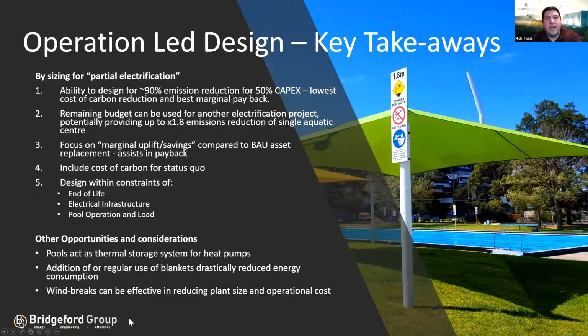So we've got a few key takeaways here, and we're terming this operation-led design. By sizing for partial electrification, you can put in a heat pump that doesn't fully electrify the site, sizing it for, say, half capacity, 800 kilowatts instead of 1600. You actually get close to 90% of the emissions reduction, because those heat pumps run so many hours in the year, and the pools themselves are a bit like thermal storage tanks.